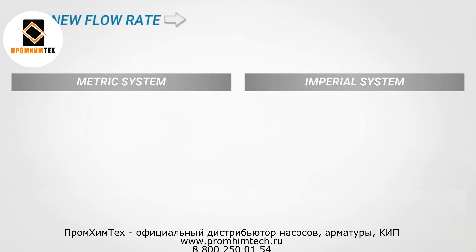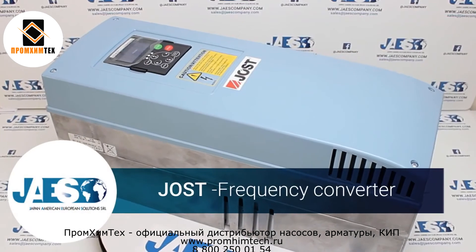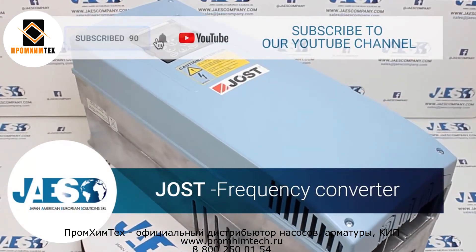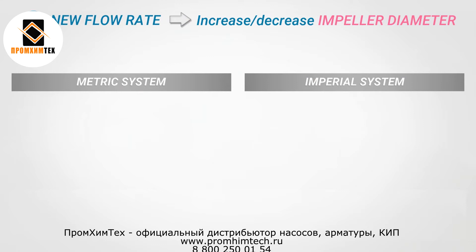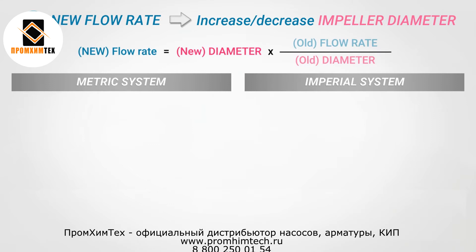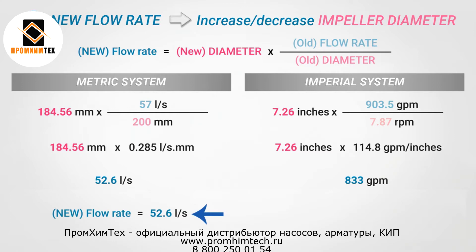Now we are going to calculate the new flow rate in the case we need to change the diameter of the impeller. Changing the impeller size by adding or subtracting material is not the best solution — a good way is to use a frequency converter to change the pump speed and keep the design criteria intact. But if you are trimming down the impeller diameter, then the new flow rate equals the new impeller diameter multiplied by the division of the old flow rate by the old impeller diameter. Using these values, we get 52.6 liters per second, or 833 gallons per minute.